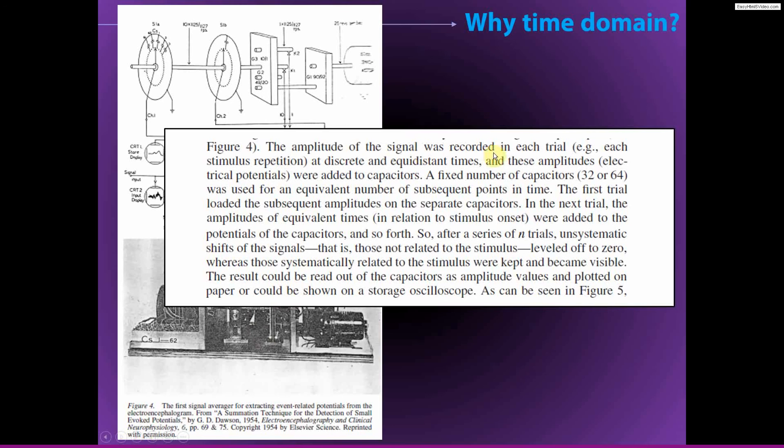This is a screenshot of the figure legend describing how the machine works. So the amplitude of the signal was recorded in each trial, each stimulus representation, at time points, equidistant, and these amplitudes were added to capacitors, so physical capacitors. A fixed number of capacitors was used for an equivalent number of time points. And so this means that the sampling rate of the data was defined by the number of capacitors that you had built into this machine. It's quite remarkable. Now the first trial loaded the subsequent amplitudes. These are the EEG amplitudes on each separate capacitor. In the next trial, the amplitudes of equivalent times relative to stimulus onset were added to the potentials of each of the capacitors. And so after a series of N trials, unsystematic shifts of signals leveled off to zero. And those systematically related to the stimulus, which are the event-related potentials, were kept and became visible. They could be read out of the capacitors and plotted on paper or shown on an oscilloscope.